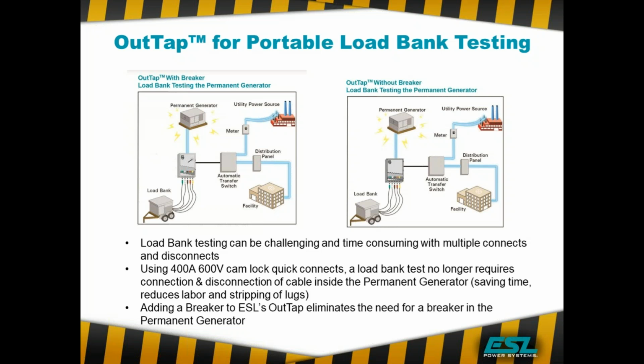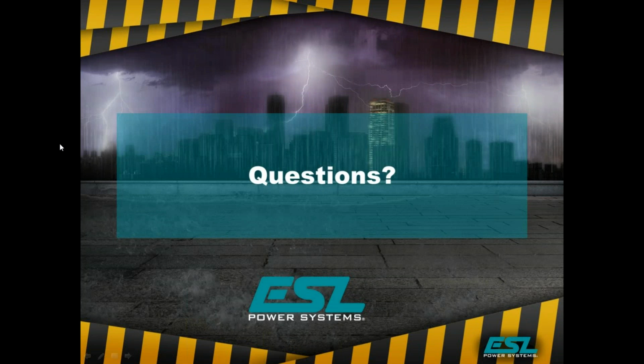We can put a shunt trip if you get it with a breaker. We can put a shunt trip on this breaker so that if you lose power during a load bank test, it'll open up that breaker and power can be provided to the facility. So that's it. Questions?